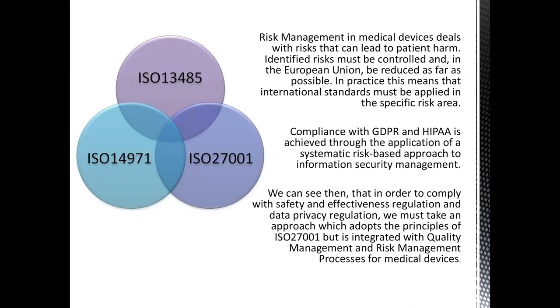Risk management in medical devices deals with risks that can lead to patient harm, and identified risks must be controlled and, as I've mentioned, in the EU be reduced as far as possible, which means complying with international standards. So we can see that in order to comply with safety and effectiveness regulation that includes information security and data privacy, we must take an approach that adopts the principles of ISO 27001, but in a way that's integrated with quality management standards and risk management standards for medical devices.